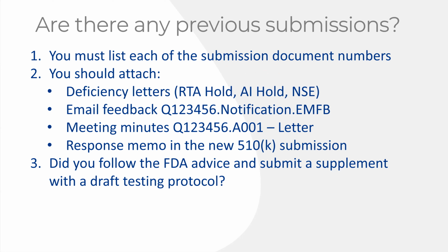Are there any previous submissions? So this is something a lot of clients, they will have already done a pre-sub and then they'll start hunting for somebody to help them with their 510K. If that is your company, make sure you share those pre-submission meeting minutes with us so we can reference it in the submission. That's a requirement. And then any concerns that the FDA made during the pre-submission meeting, in their email response or during the actual meeting, if you had a teleconference, we need to address those in a response letter that you attach to your eSTAR or your eCopy.